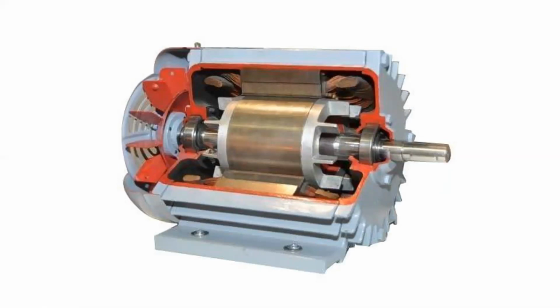And what you'll notice from this picture is that there are no electrical connections made to the rotating item in the middle, the rotor. There are no brushes, there are no connections, there are no electrical wires that connect to this item here. It is simply suspended by two separate bearings, one at the front, one at the back, and it turns by twisting it with a hand if it's not energized.